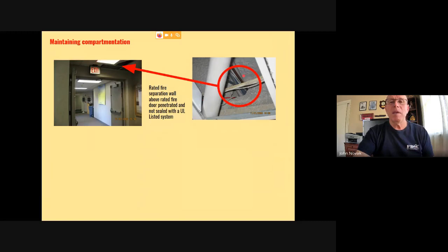So the issue with maintaining this fire compartmentation is everything has to work. So the fire doors have to close properly, right? They have to latch. Here's a picture that I took on an inspection. The ceiling just happened to be open, all right? So when I looked up in there, I could see penetration. So some contractor punched a hole through the concrete wall to run IT cable and other cables. So this 3-hour rated wall now is 0 rated because we can have products of combustion pass right through from this side into this side. So our area of refuge is now violated.